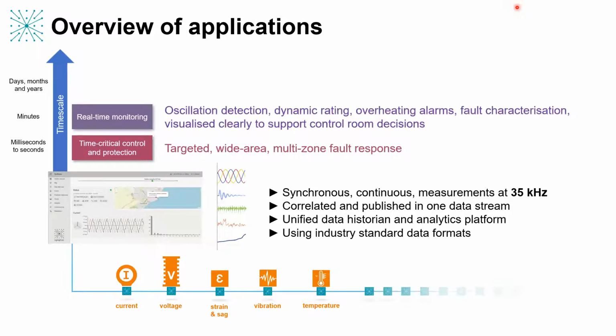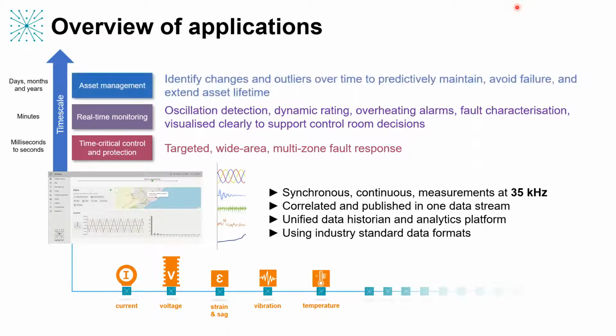But then, using that same data, you can derive things on the timescale of, say, minutes to hours. In that case, we're talking about synchrophasors, subsynchronous oscillation, dynamic rating of lines, overheating alarms on cable terminators, and characterization of faults when they happen, for example with correlation with what's going on mechanically on that system, to try to determine why the fault occurred and what type of fault it is, so that you can respond more precisely. And visualizing data so that rather than it just being pure publishing on process bus machine-to-machine operations, humans can start getting involved and seeing how their system is performing live.